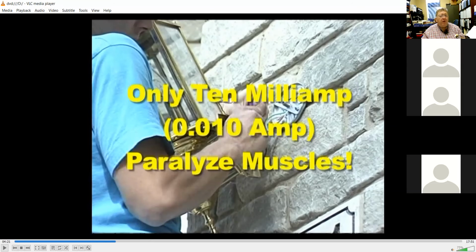So if you have a new installation now, a new house wired, then all of your living quarters have to have arc fault breakers in the panel. And every area in the house has to have it except for the bathroom. And the bathroom has to have that right there. In the kitchen, you've got to have arc fault and ground fault protection.